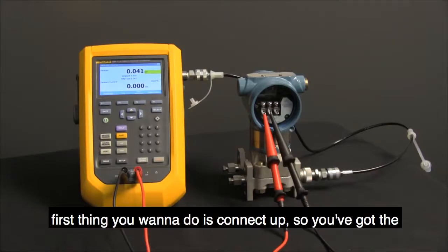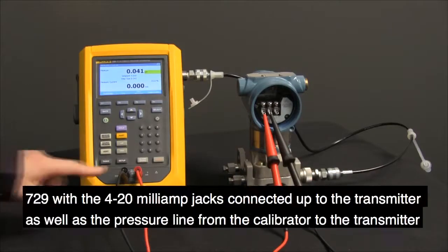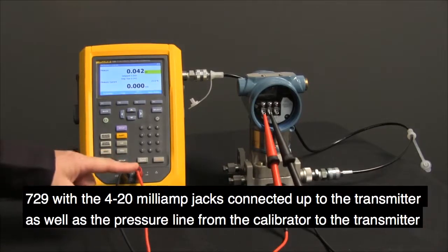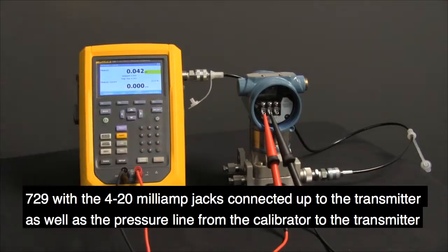First thing you want to do is connect up. You've got the 729 with the 4-20 milliamp jacks connected up to the transmitter as well as the pressure line from the calibrator to the transmitter.